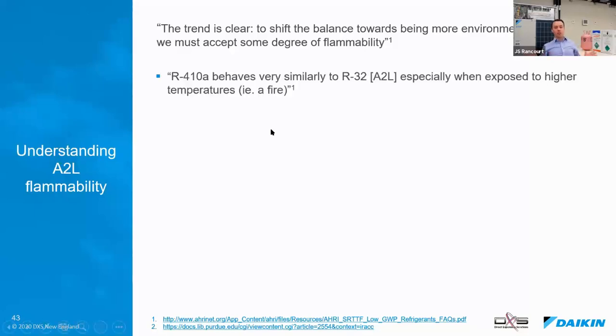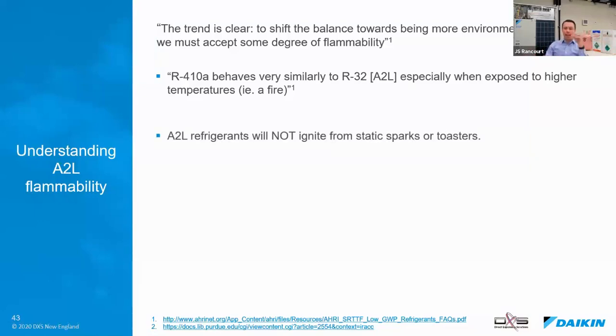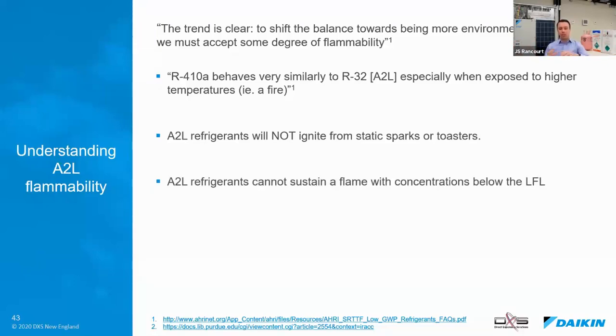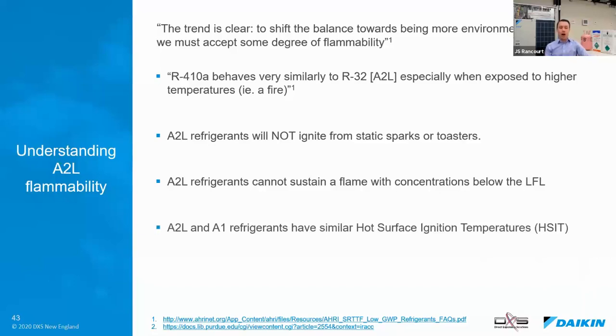Let's understand, first of all, that R410A behaves very similarly to R32, an A2L refrigerant, when exposed to higher temperatures in a fire. An A2L refrigerant cannot get ignited from static sparks or toasters or intermittent sparks. The A2L refrigerants cannot sustain a flame with concentrations below the lower flammability limit, which the codes or the standards are addressing. They have similar hot surface ignition temperatures. That acronym is going to start being discussed quite a bit.